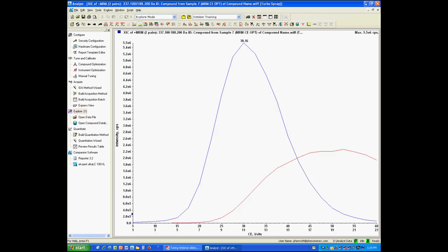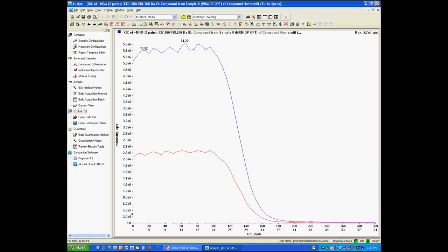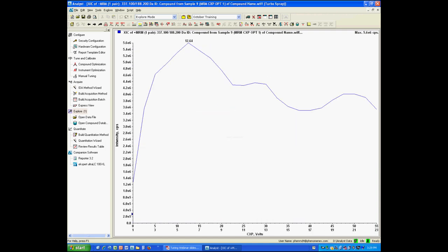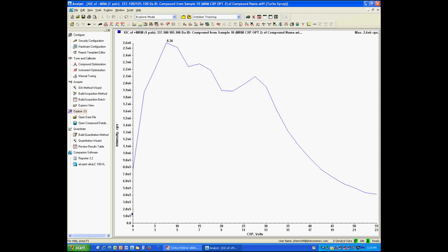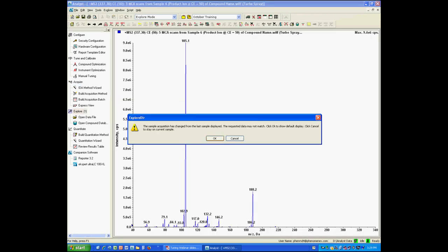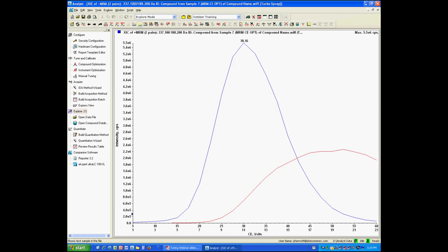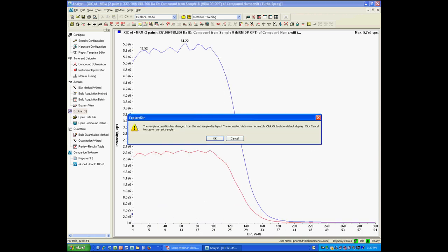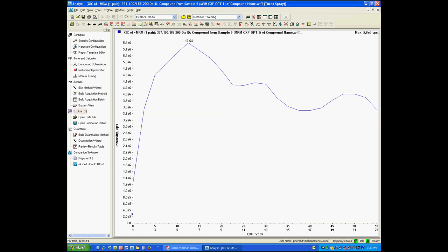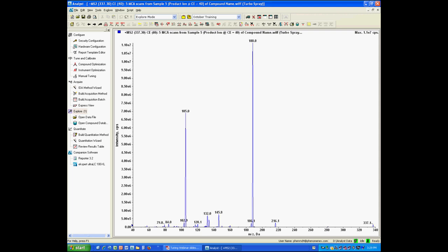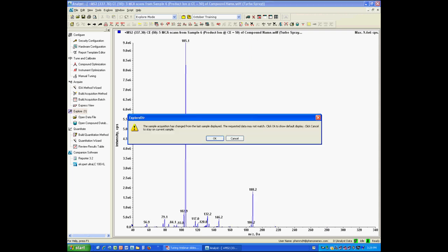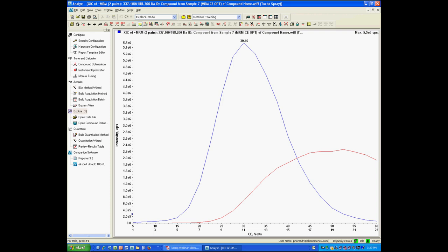And this is really good to have as kind of a backup information if you lose your tune files or your acquisition method disappears. You will have a file where you can go back and find your transitions and find your Q1 mass and find the declustering potential. Always make sure the declustering potential matches for all transitions. Here we have the CXP of the first transition. You can see the 337.1 to the 188.1, and the second 337.1 to 105. Right, you can go ahead and close out of that.